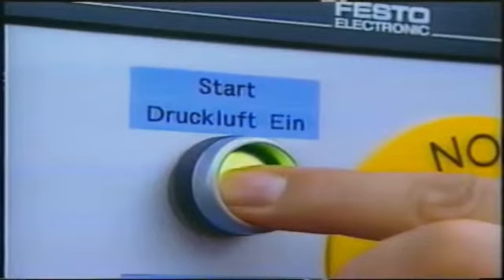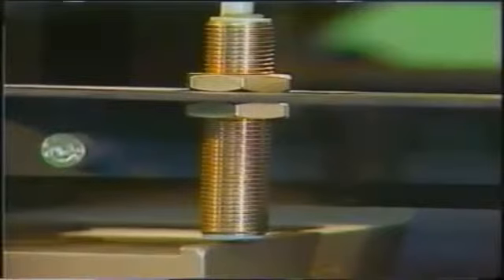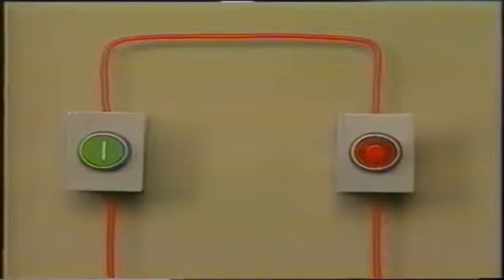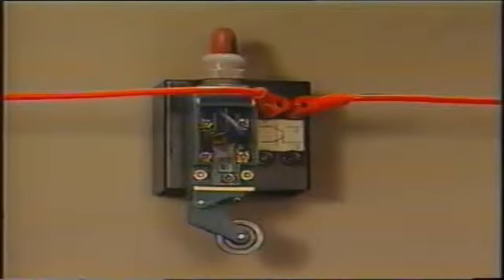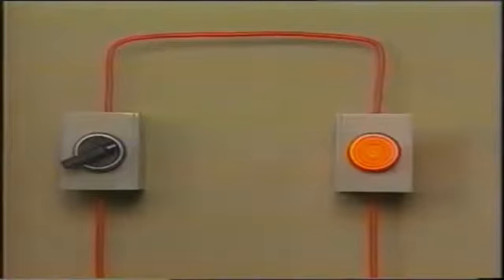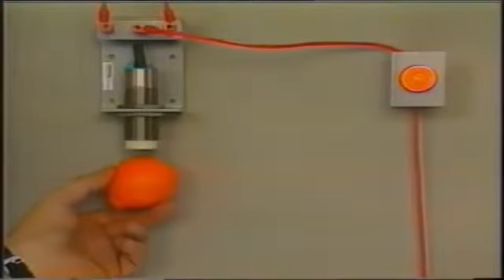A differential pressure switch has two pressure chambers, separated by a metal diaphragm. If the pressure in the upstream chamber rises because of increasing contamination of the oil filter, an increasingly large pressure differential results between the two chambers. This causes the diaphragm to bend. This in turn pushes a pin into the field of an inductive sensor, and an electrical signal results. All signal elements we have looked at here have one thing in common, whether a manually actuated switch, a sensor, or a pressure switch. It is always an external influence that triggers the electrical signal at the signal element, causing the circuit to be opened or closed.